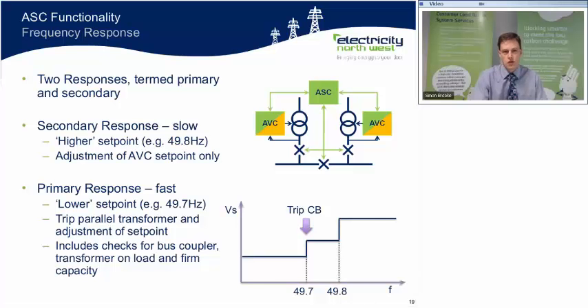There are two responses, which we term primary and secondary response. So dealing with the secondary response first, this is a slow response, and when the frequency reaches a set point, for instance 49.8 Hz, the ASC issues an adjustment of the AVC set point, the voltage set point, to the AVC relays. Now, this can take some time to have an impact because of the time taken for tap changes to operate.